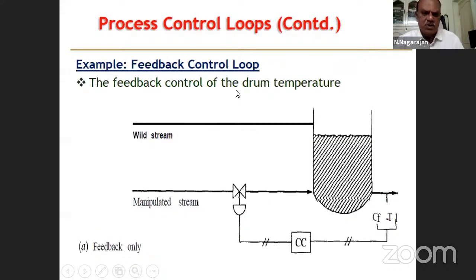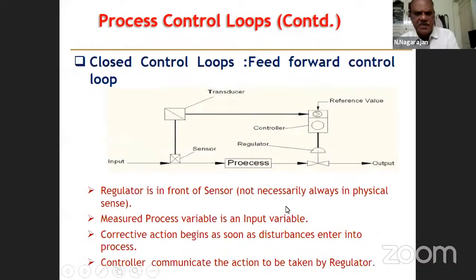Feedback control loop of the drum temperature. This is some example. Okay, there is steam going there and heating the contents in that. This is the main input stream. So you measure the temperature, then the comparator or the controller compares the measured temperature and the set point. Then accordingly it manipulates the steam. This is one example. And the next important type of control loop is the feed forward.